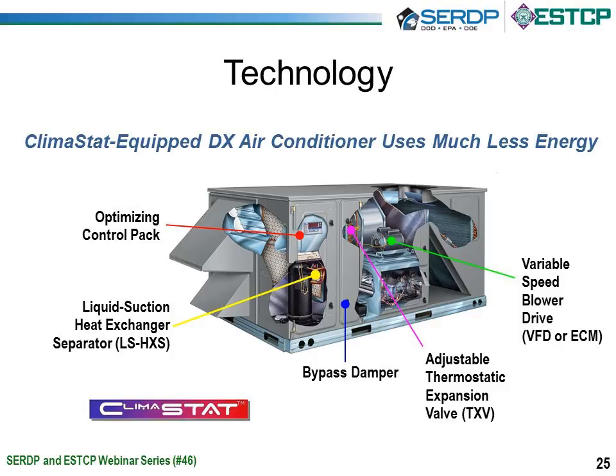Okay. These are the 5 things that we either add or change. We either add an optimizing control pack, which optimizes the operation of all of the components, the fans, blowers, and compressor, or we can use a standard PID temperature controller, which is lower cost. It depends on the application and the economics. We add a liquid suction heat exchanger separator. This is a heat exchanger that has no moving parts. We add a bypass damper, and the damper also has an actuator.